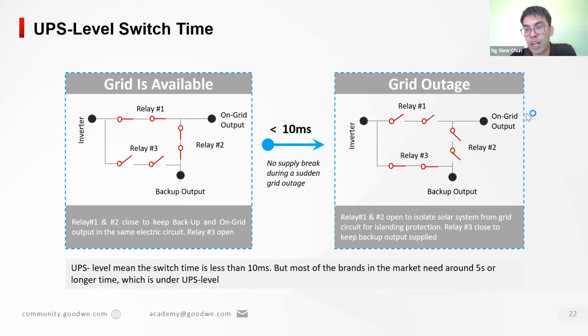But during a power outage, when there is no power from the grid, this relay will be open and this relay will be closed. This is extremely important so that we achieve the anti-islanding function, ensuring the safety of the maintenance technicians of the grid operator, so that the grid-connected output is not energized. At the same time, any critical load within the household will still continue to be powered by our inverters. So this functions like an ATS and it is integrated in our residential inverter. And we can achieve a 10 millisecond UPS level switch time.